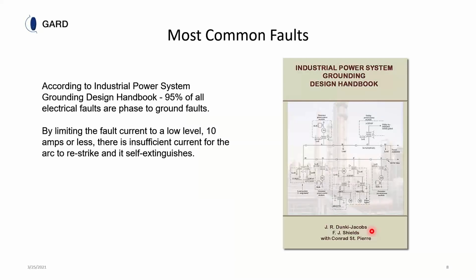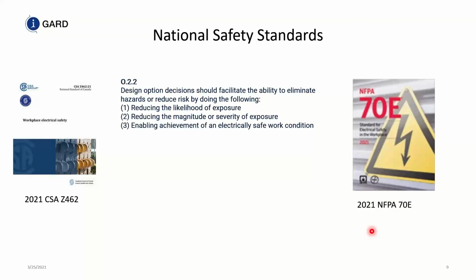So by limiting the fault current to a low value, so the National Electrical Safety Codes, Z462 and NFPA 70E, and these are the most current versions. They changed so slightly this year, but they always improve. Now, keep in mind that one of the questions I get asked the most is, do you have to follow NFPA 70E and Z462? Because they are not installation standards, they are safety standards, so they always apply. It doesn't matter when your installation was built or was assembled, these standards, the safety standards, apply to all installations all the time.